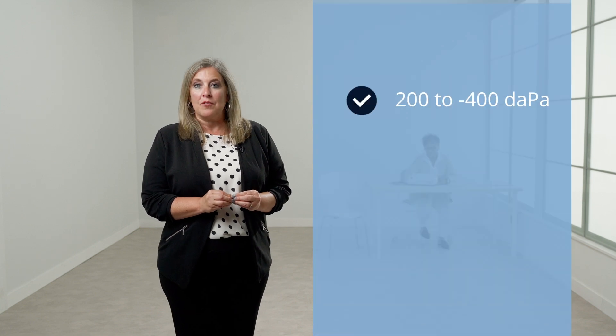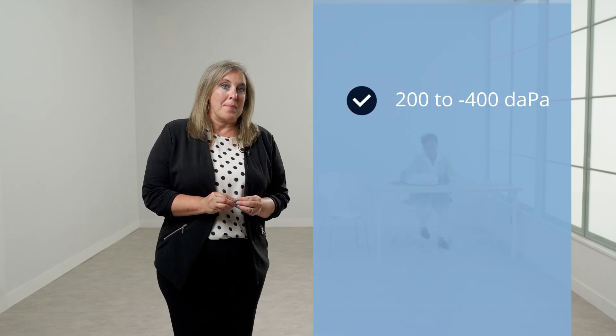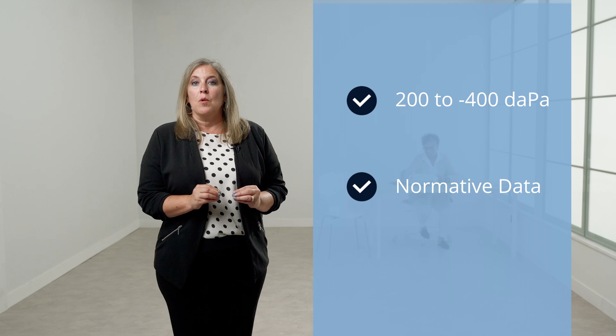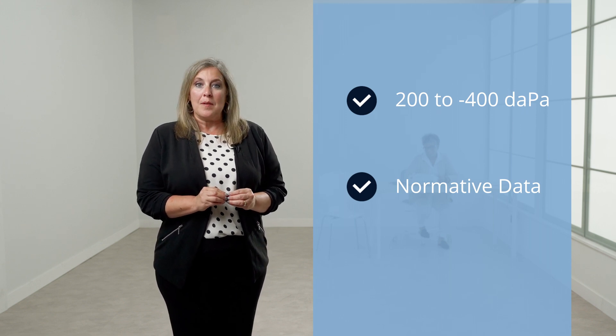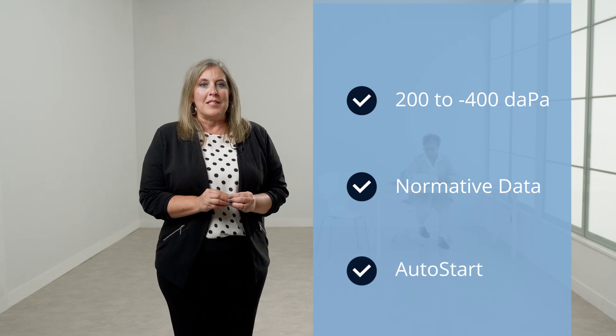The GSI 39 has an optimized pressure range and sweep speed for fast and accurate measurements. The pressure range is from positive 200 to negative 400 daPa. Normative data will be displayed on the screen of the instrument. For 226 Hertz tympanometry, the tymp will automatically pressurize and start the test when a seal is obtained. The pressure sweep will stop when the tympanogram returns to the baseline after negative 100 dPa.